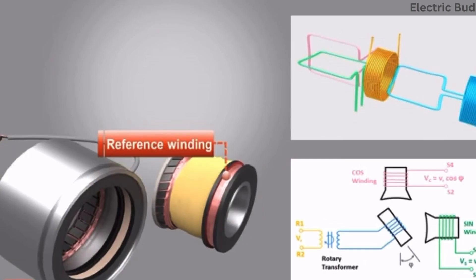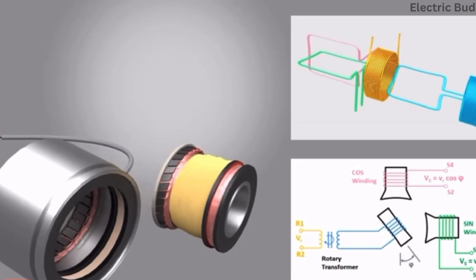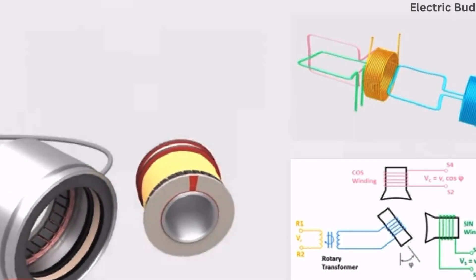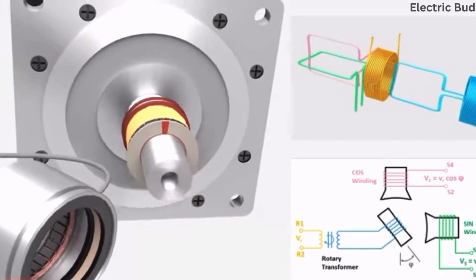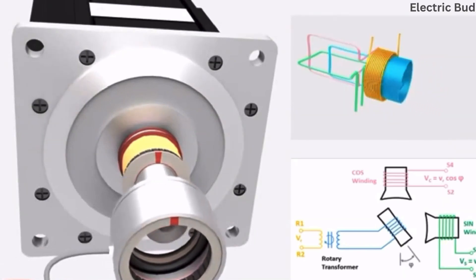measured to determine the angle of the rotor relative to the stator. To get an output signal, we have two secondary stator windings — a so-called sine and a cosine winding — which are displaced angularly to each other by 90 degrees.